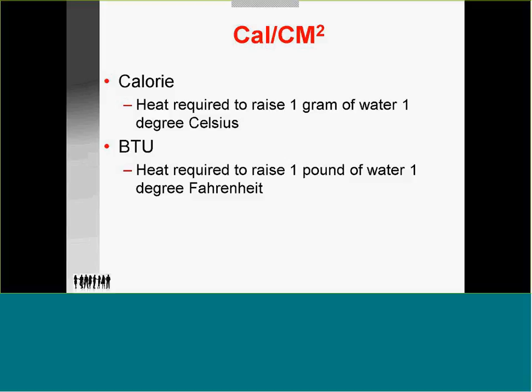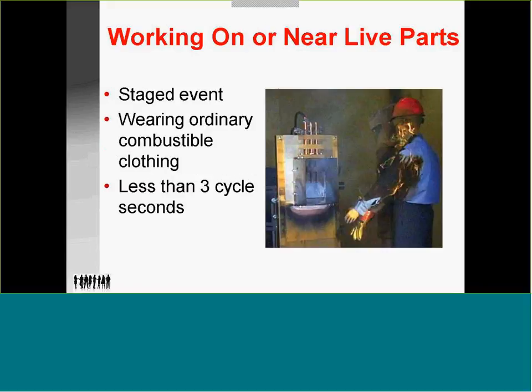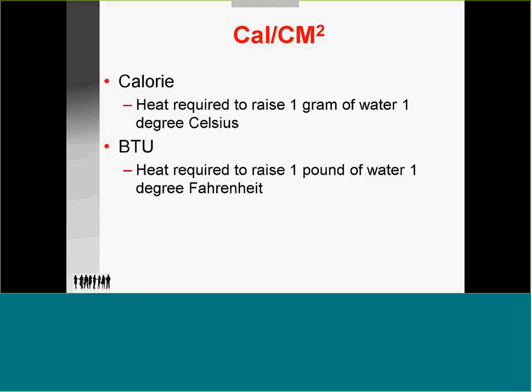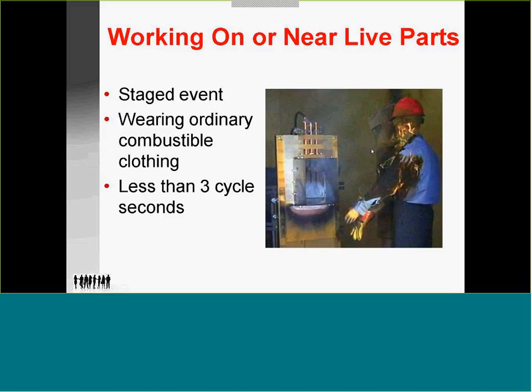A calorie is the energy required to raise 1 gram of water 1 degree Celsius. It's a heat measurement. More familiar is BTU, the heat required to raise 1 pound of water 1 degree Fahrenheit. We use calories because this is an international code. Here is a graph; this is a dummy. He's exposed to about 35 calories per square centimeter. I'm sorry, I keep hitting the wrong button there. This was a test that lasted just a little less than 3 cycle seconds using ordinary clothing, and look what happened. The face shield is an ordinary plastic grinding shield some people have been using in place of an arc-rated shield, and this ignited immediately. And in an explosion, it can actually ignite, melt, and then get pushed to the face, which is cooler, and then solidifies on the surface of the skin.